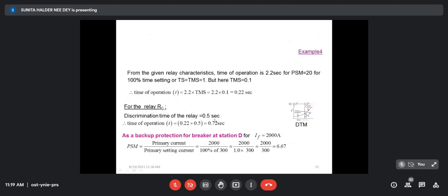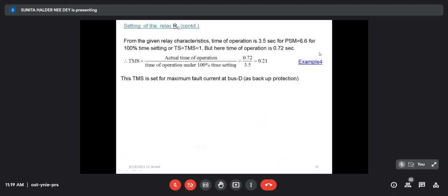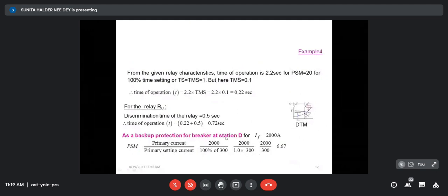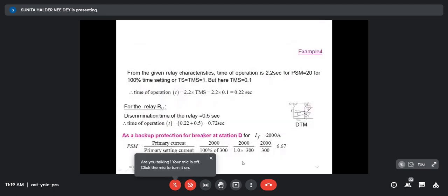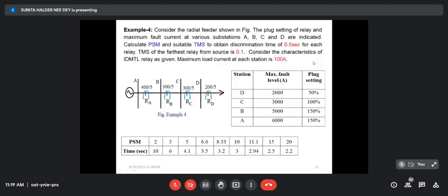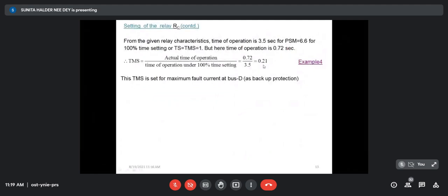For a particular TMS, the operation is at 0.72 second, but for 100% TMS (TMS = 1), it should be 3.5 seconds. So the time multiplier setting is 0.72 / 3.5 = 0.21. So 0.21 will be the TMS for relay at station C as backup protection of station D. However, there is no option of 0.21 in relay setting, so we set it to 0.2, meaning every calculation will be iterative.